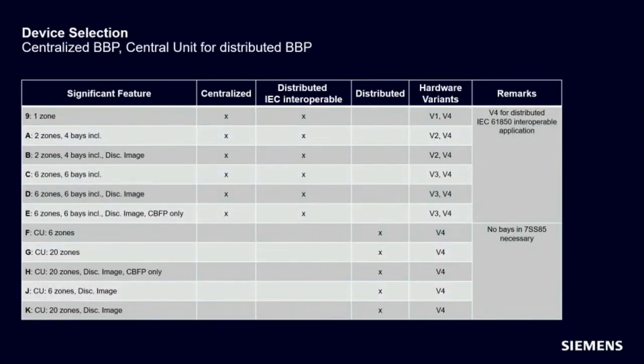A very special significant feature is a significant feature E, which also allows 6 zones and has a disconnector image, but in this very special functionality, you have only the circuit breaker failure protection available. You don't have a busbar differential protection. This is a special requirement to use a busbar protection device, the 7SS85, to use only the disconnector image of the busbar protection device to clear the associated bus zone in case of a circuit breaker failure.